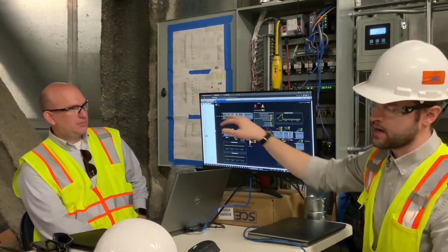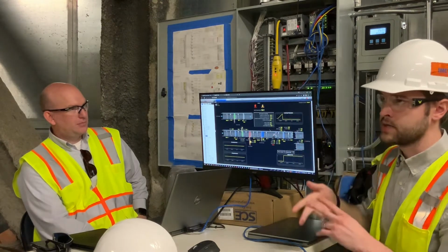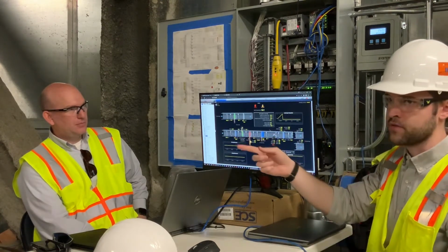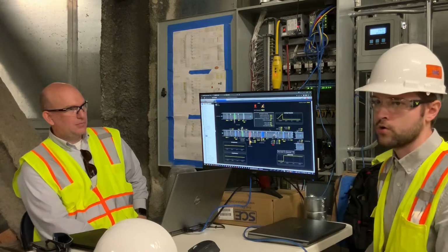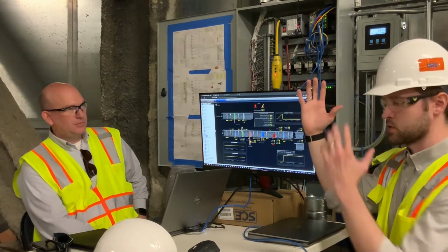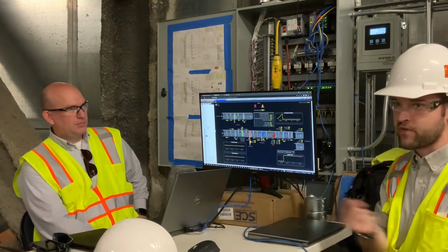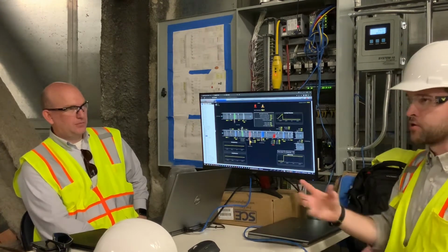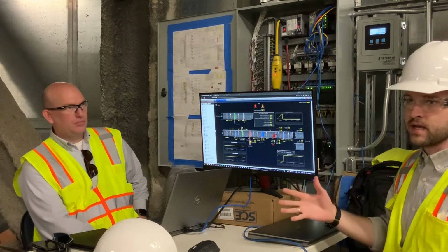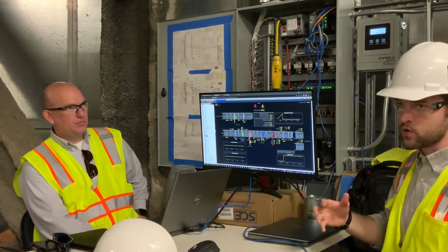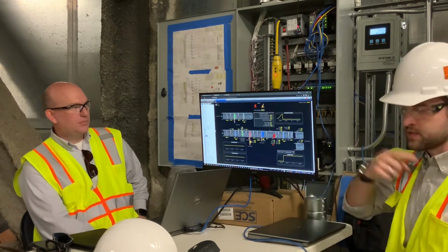On the exhaust side, rather than the two sensible and total energy wheels you have in air handlers 1 through 4, you have a glycol loop. Basically you have a coil in your exhaust stream, you have two pipes, you have a set of pumps, and you have a coil in your supply. Under certain outside air conditions, it enables that system for either heating or cooling, and it just runs those pumps and circulates the glycol.